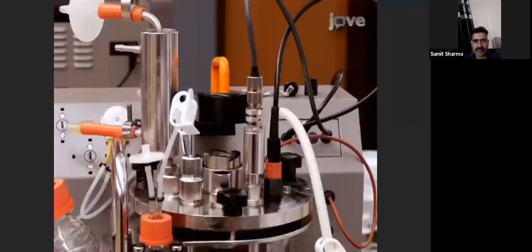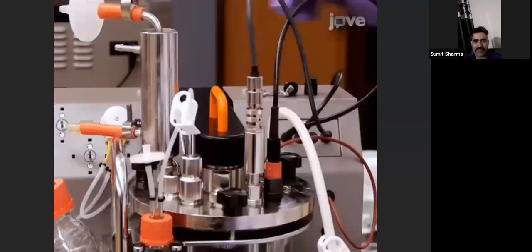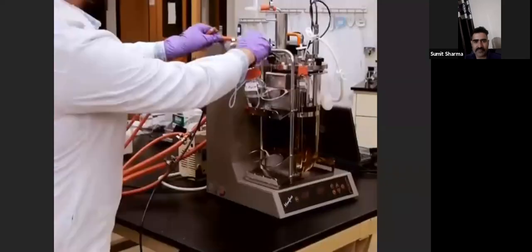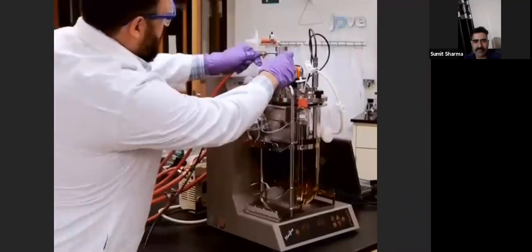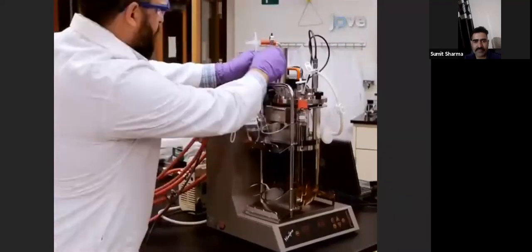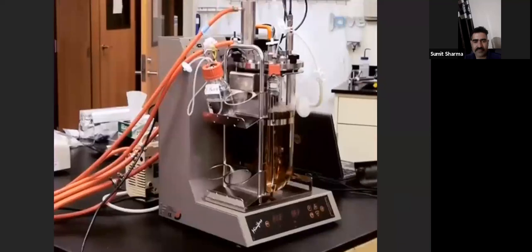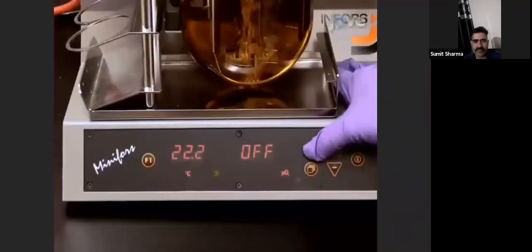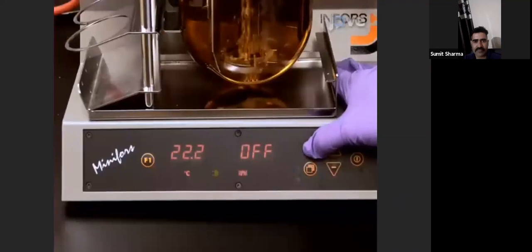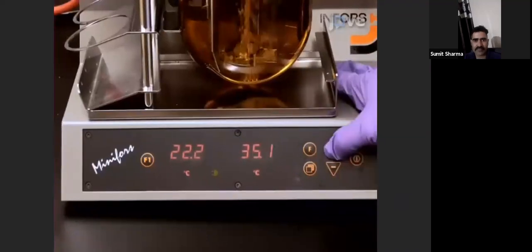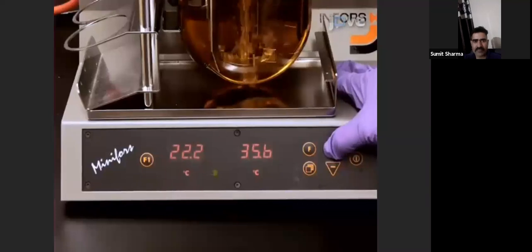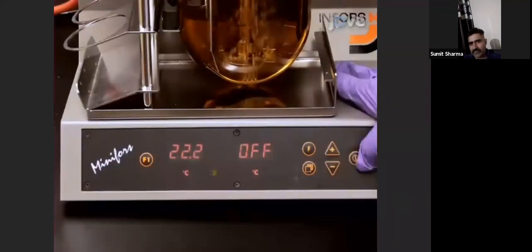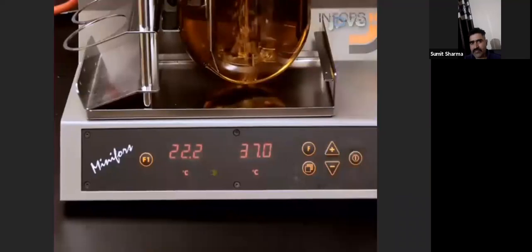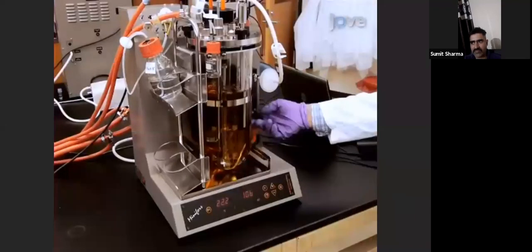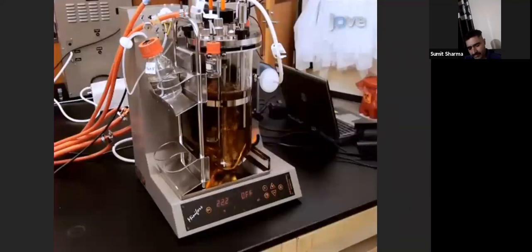Lower the agitation arm onto the vessel's impeller coupling. Make sure that the fermenter is on. Check that water is available to the fermenter. Turn on the air supply to the fermenter. Scroll to the temperature parameter and set the temperature to 37 degrees Celsius. Press the Enter button to start the temperature control. The vessel will heat up in 15 minutes or less. Turn the gas flow to 1 vessel volume of media per minute or less. For this setup, gas flow is 3 liters per minute.